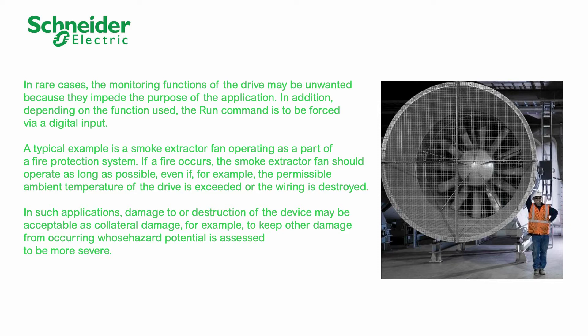If a fire occurs, the smoke extractor fan should operate as long as possible, even if, for example, the permissible ambient temperature of the drive is exceeded or the wiring is destroyed. In such applications, damage to or destruction of the device may be acceptable as collateral damage, for example, to keep other damage from occurring whose hazard potential is assessed to be more severe.